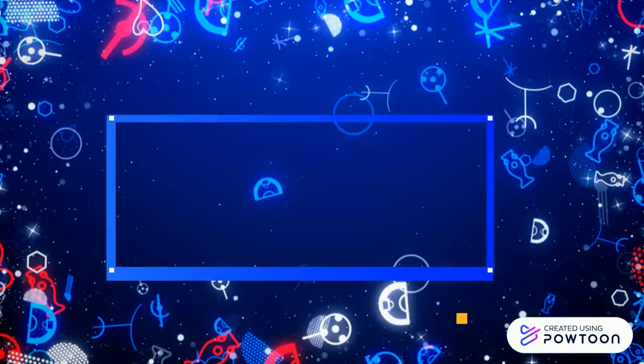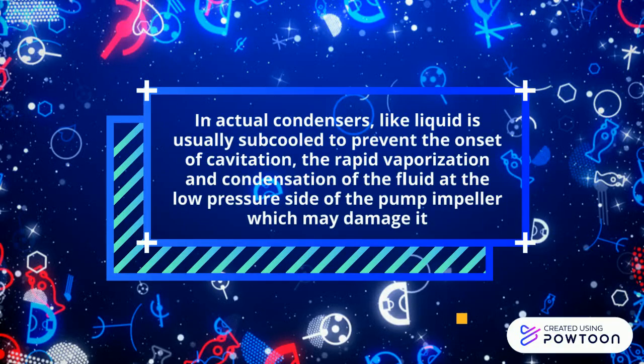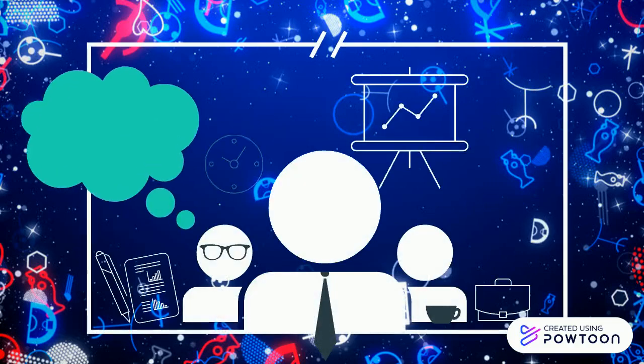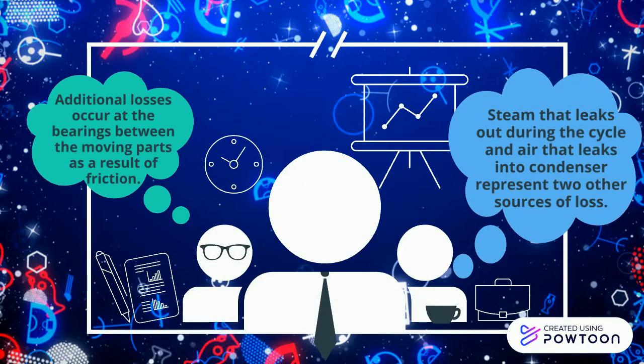Another factor that needs to be considered is actual condensers. For example, the liquid is usually subcooled to prevent the onset of cavitation, the rapid vaporization and condensation of the fluid at the low pressure side of the pump impeller, which may damage it. Additional losses occur at the bearings between the moving parts as a result of friction.